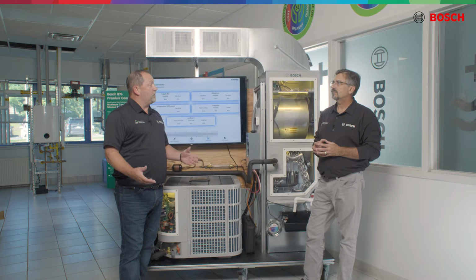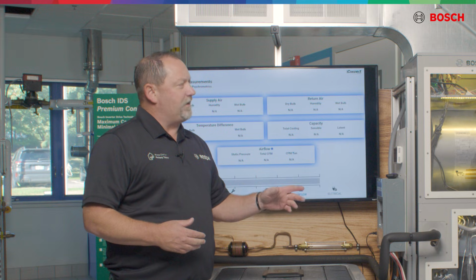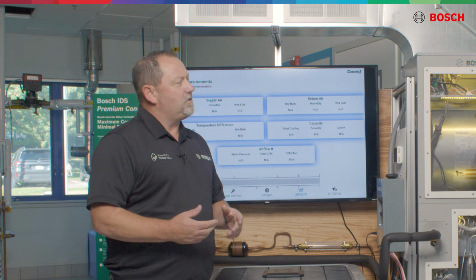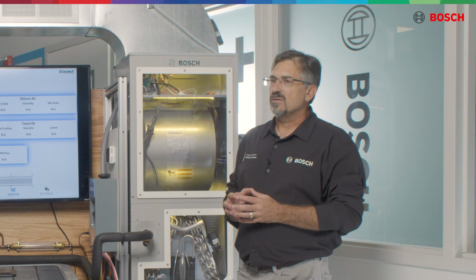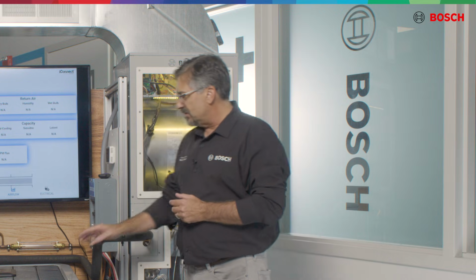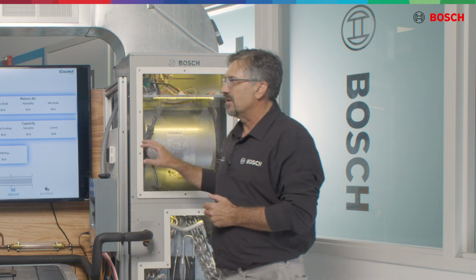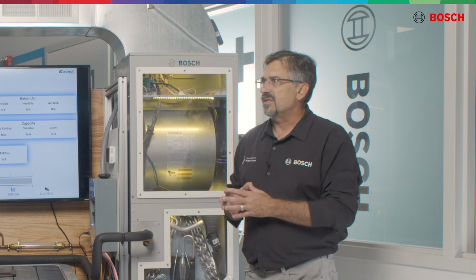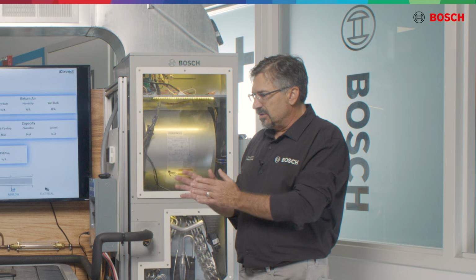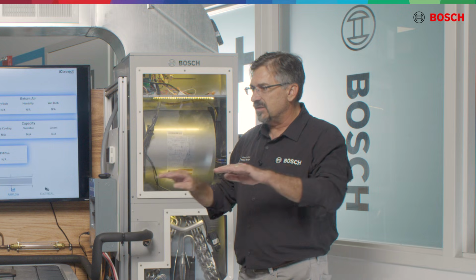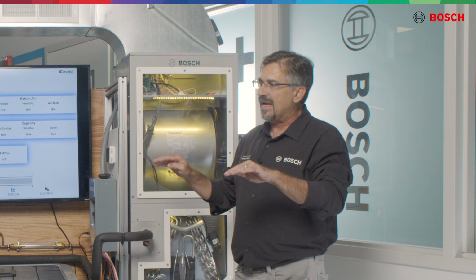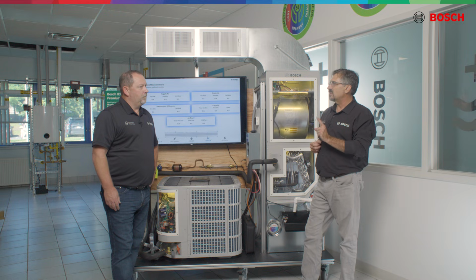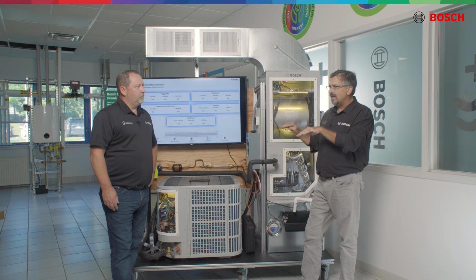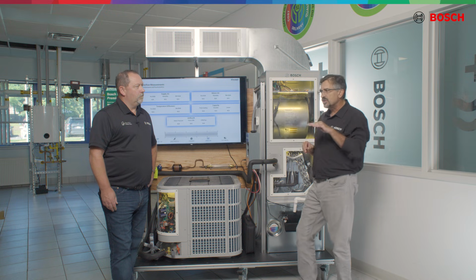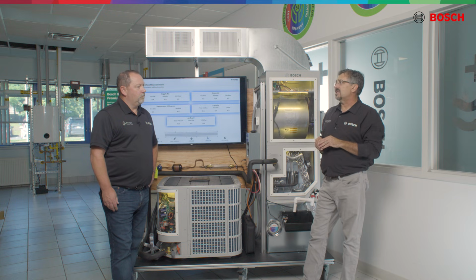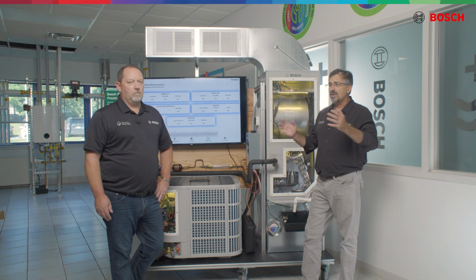Okay, so we're talking about this inverter technology, but you also mentioned load matching. So tell me what load matching really means, because I think this is where people get lost. Okay, when we're discussing load matching, what we're essentially referring to is the ability to adjust the capacity output of our outdoor unit to feed our indoor unit. So the compressor is essentially going to operate and use the indoor conditions. So if I have a house that's neutral in conditioning, it's only going to use what capacity it needs to deliver. When we have a single speed compressor, it's unable to detect hot, humid air introducing into the system. So it just runs. Consumes a lot of unnecessary power to deliver a capacity output that we no longer need.